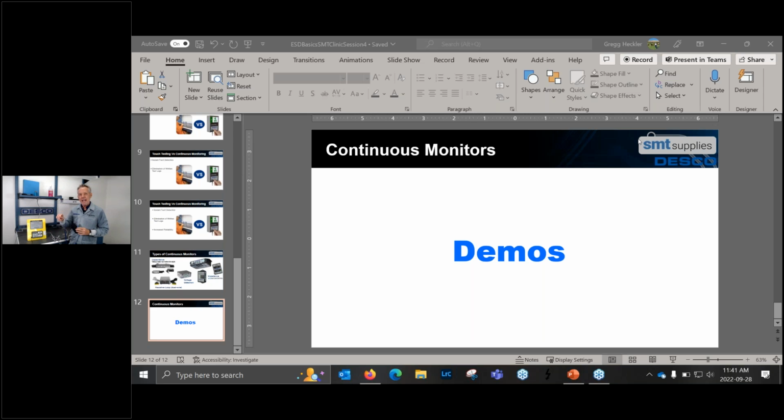And speaking to that, I can tell you, I've been doing this a long time. I've never gone into a customer and seen a fail on a written sheet. And what are the odds of that? So if you have them now, or if you ever install continuous monitors, you're probably going to find out that you actually have some broken cords or things that you never knew about. Employees just tend to write the date on there and a pass and go to their workstation. Any more questions, Jeffrey?